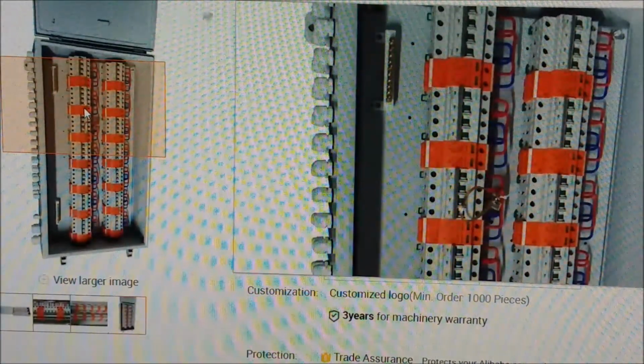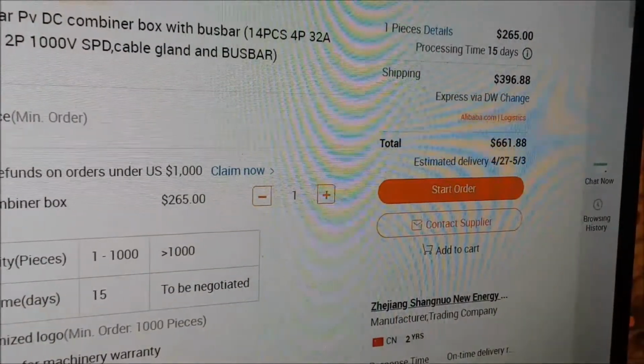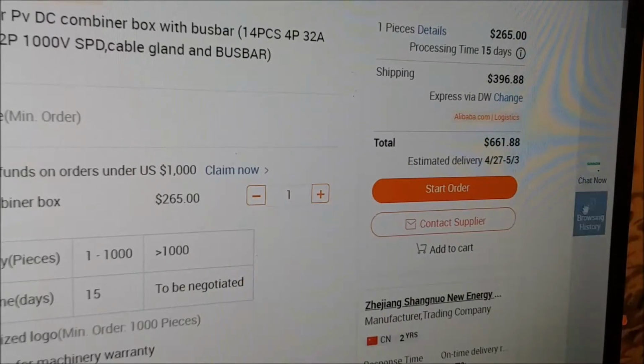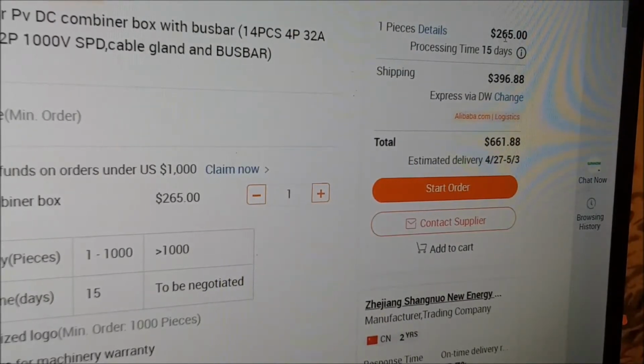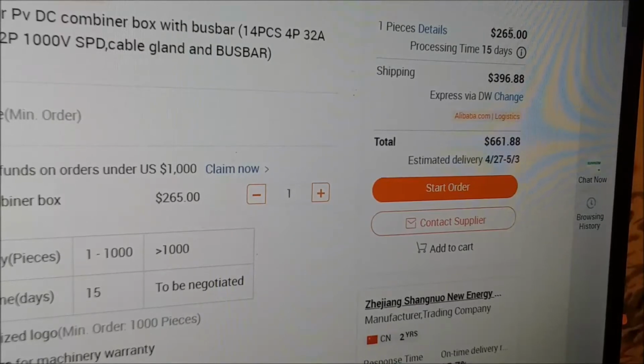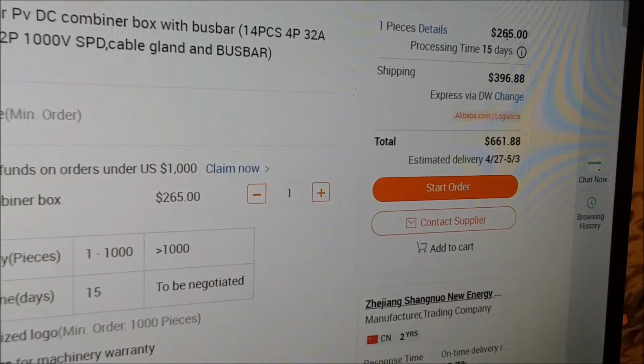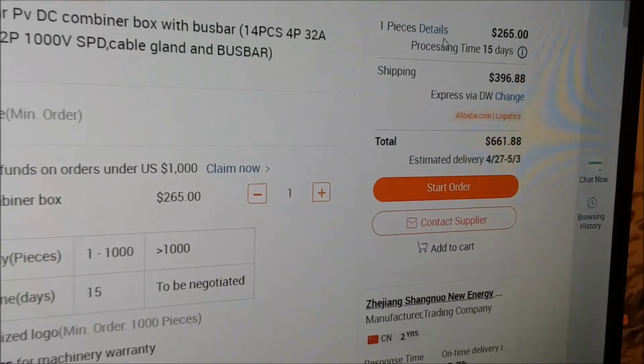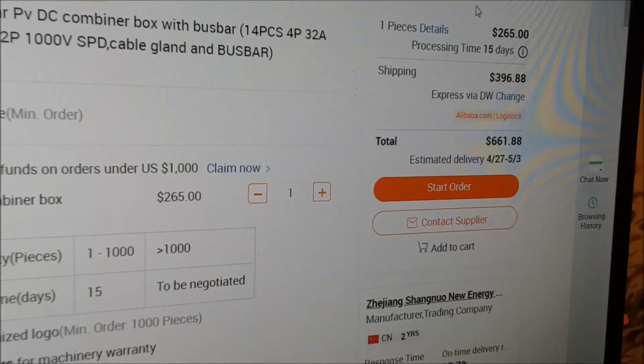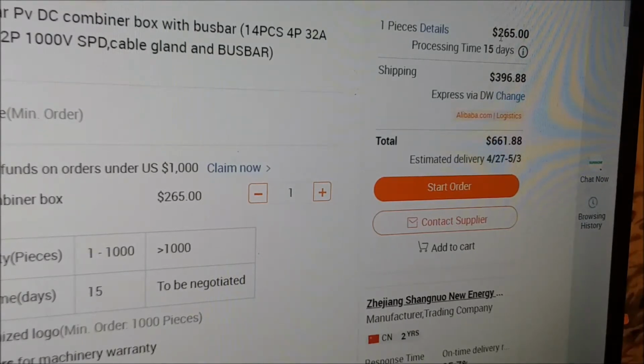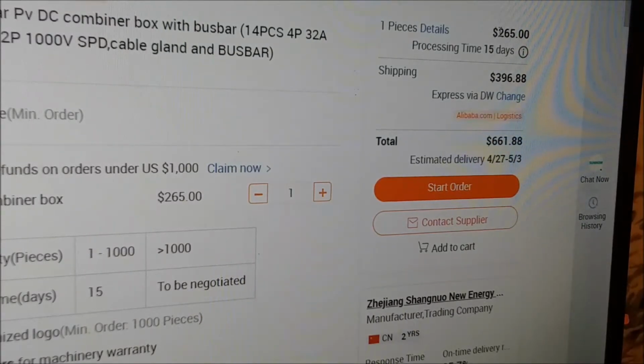The higher end boxes have that. Now, let's get to price. Over here you see at the top, $265 per piece. So instead of paying $160 for a 2-circuit one, for $265 you get 14 of them. Where we would have had to have 8 combiner boxes at $160 apiece, we have one at $265 apiece. So there's a tremendous savings.